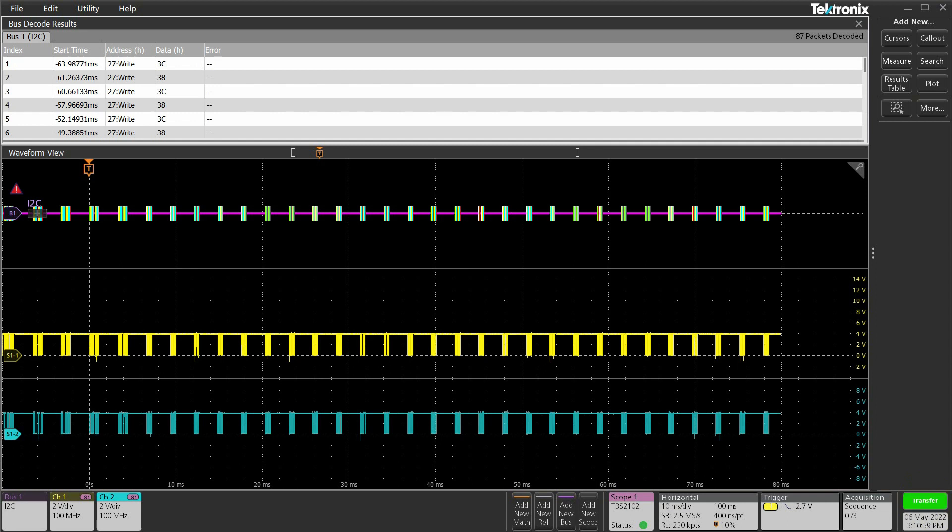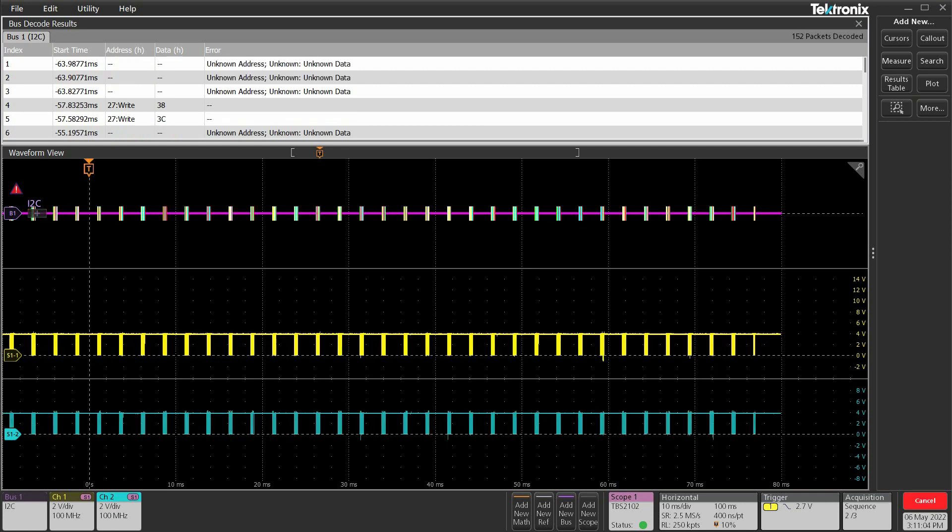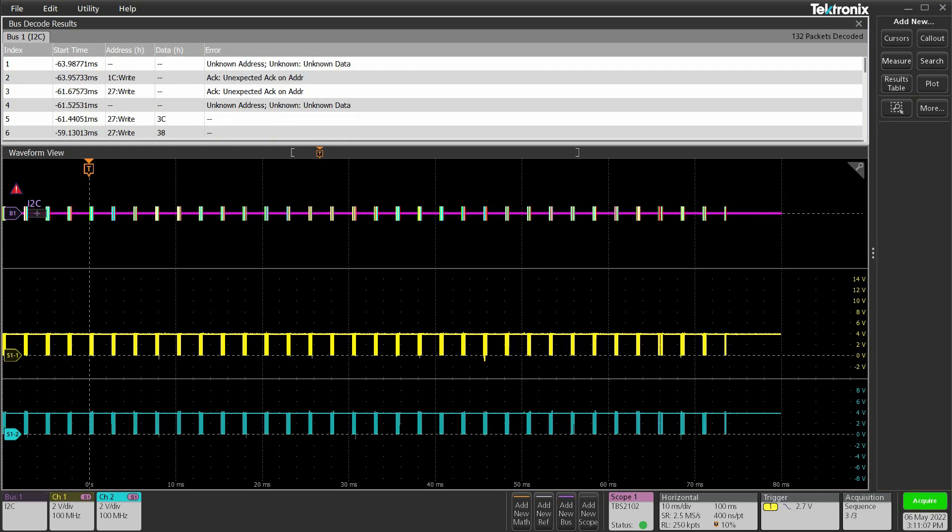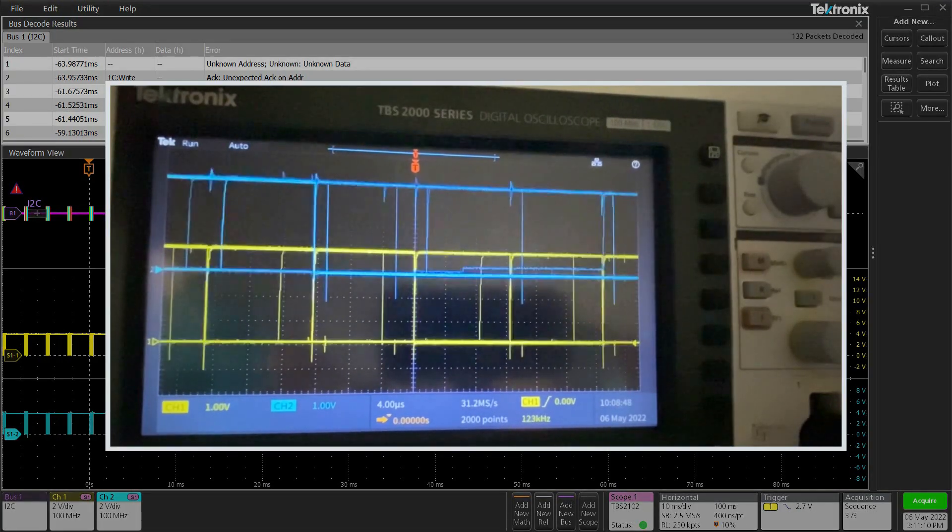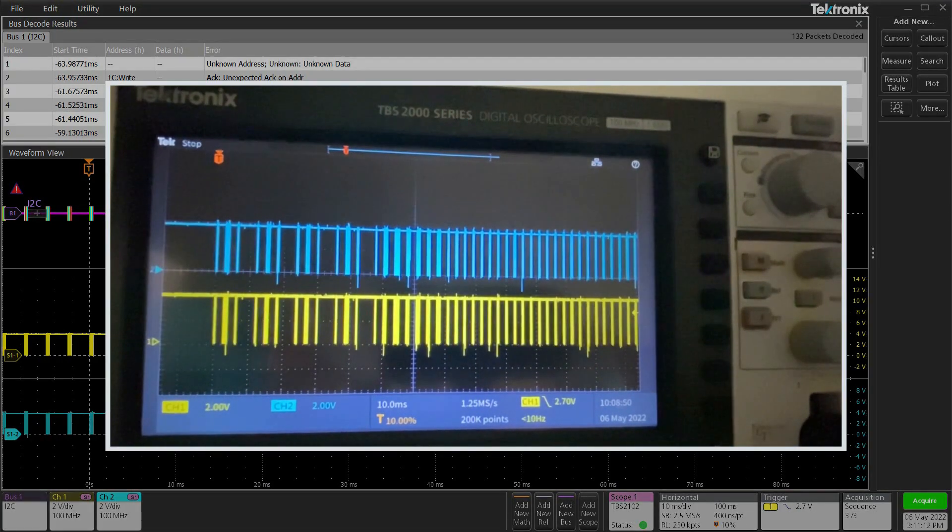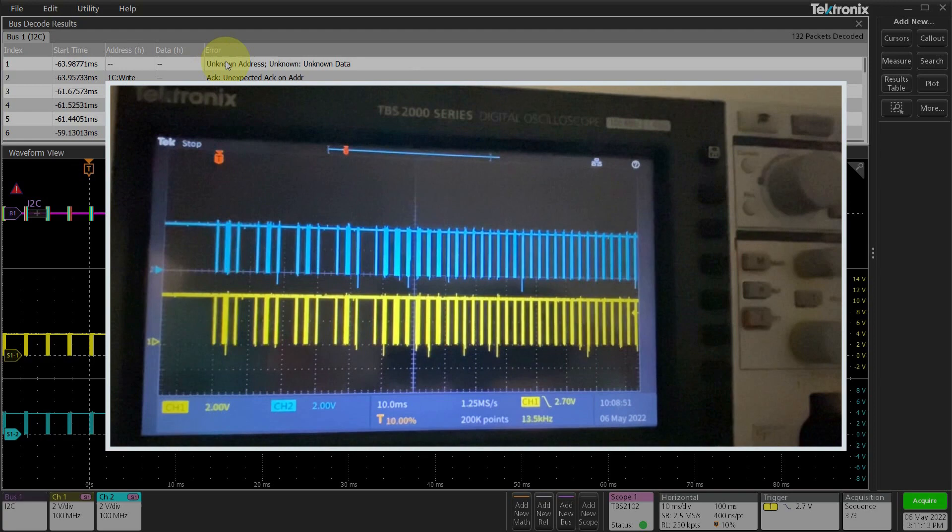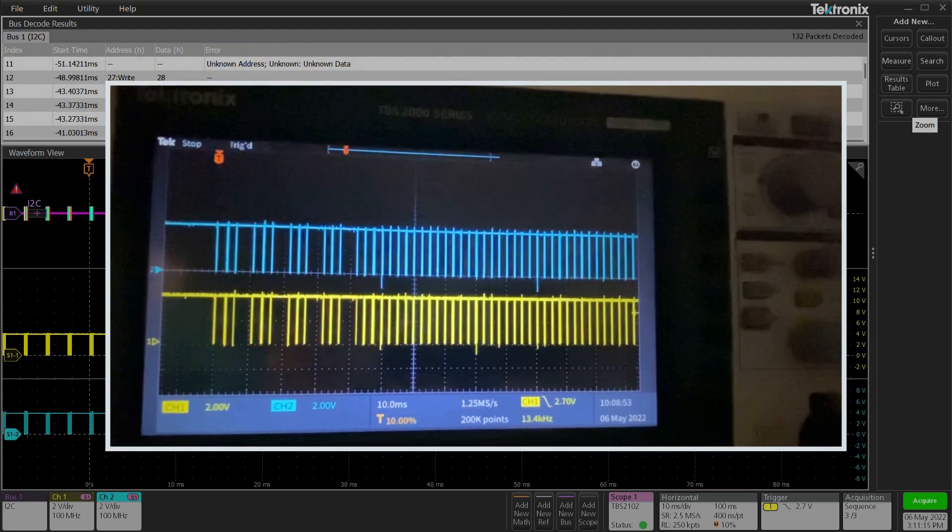Looks like our trigger worked. We are capturing waveforms meeting our trigger conditions. Oh by the way, remember the remote control feature we turned on at the beginning? Because of that, see how the vertical, horizontal, and trigger settings got propagated from TekScope to the actual scope as well.